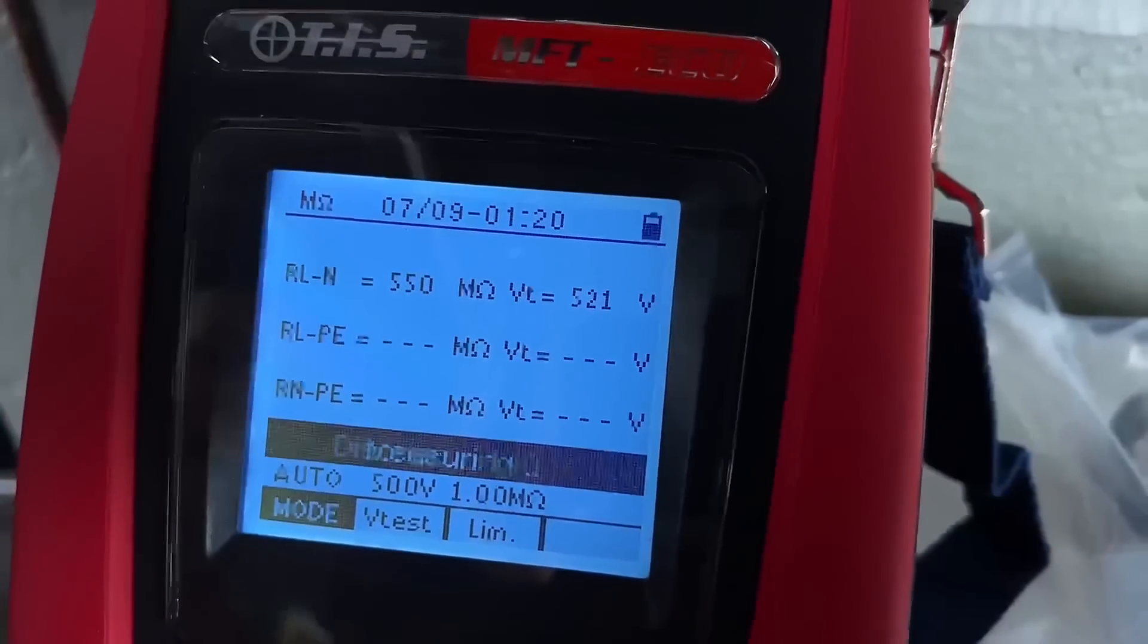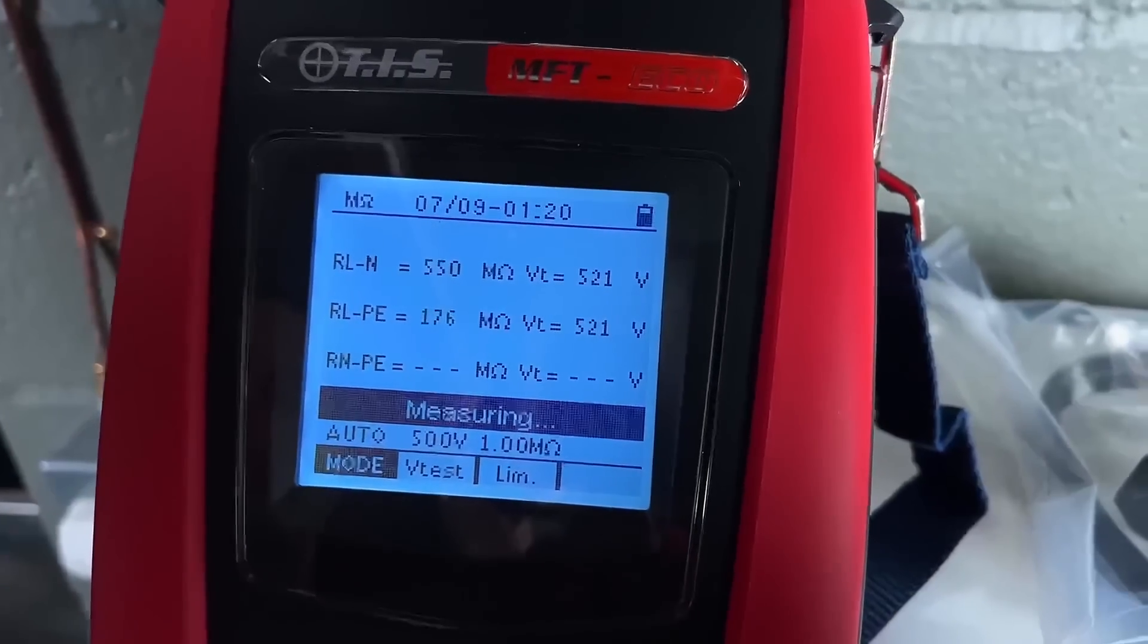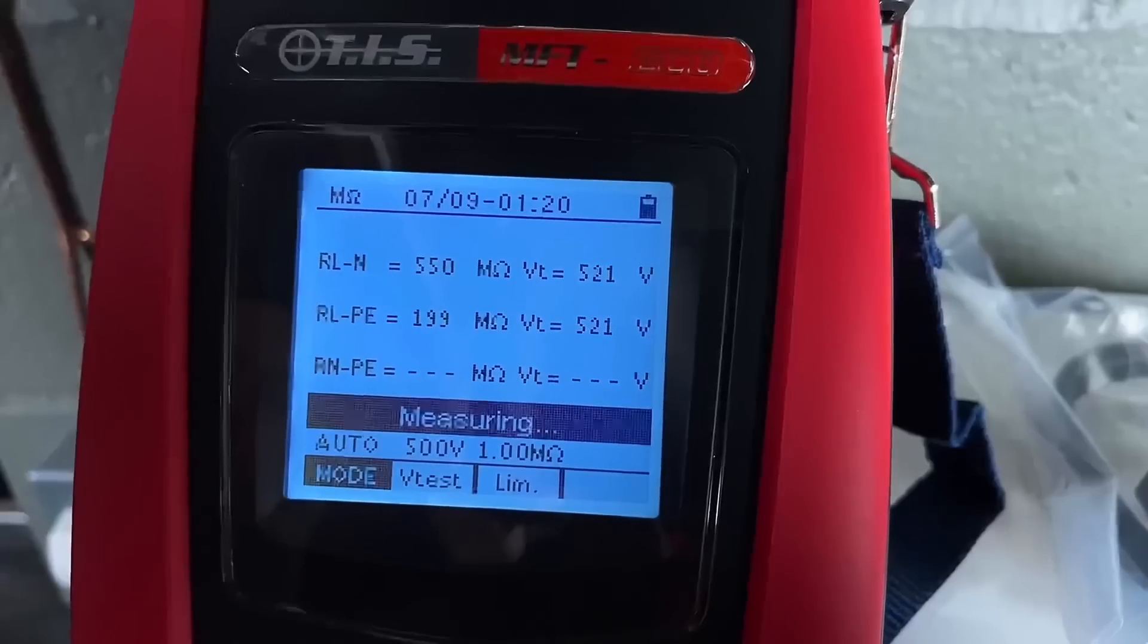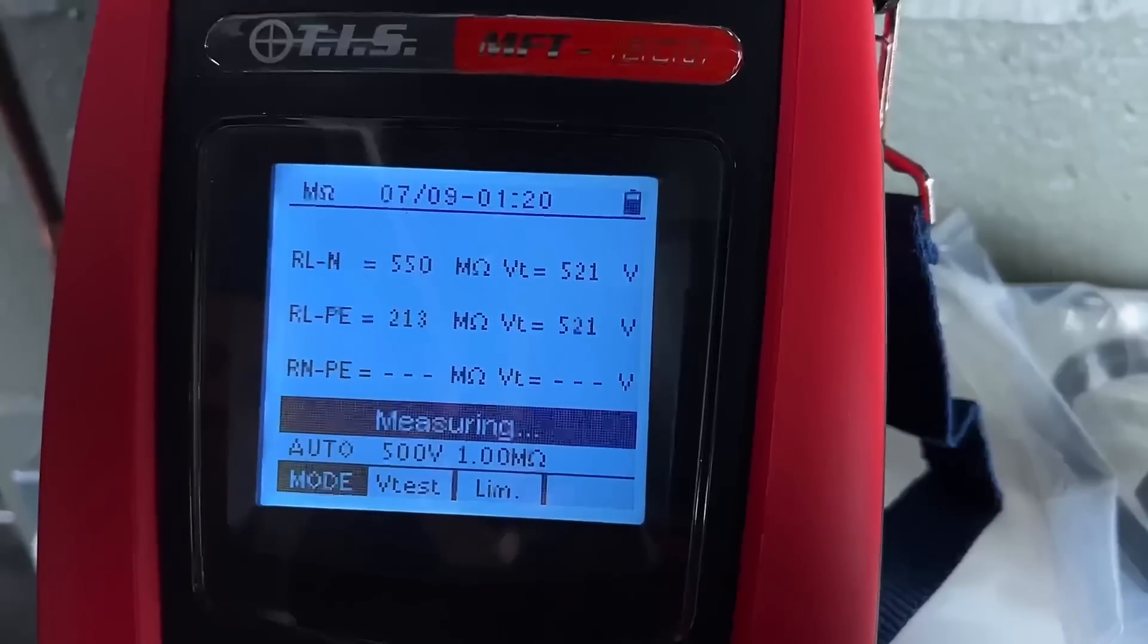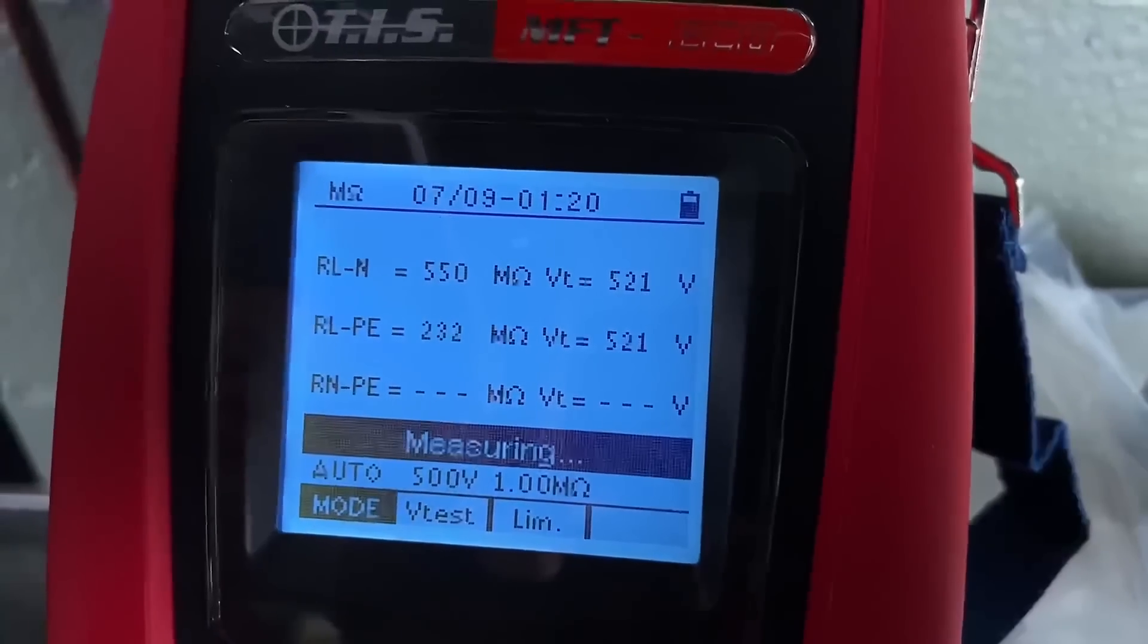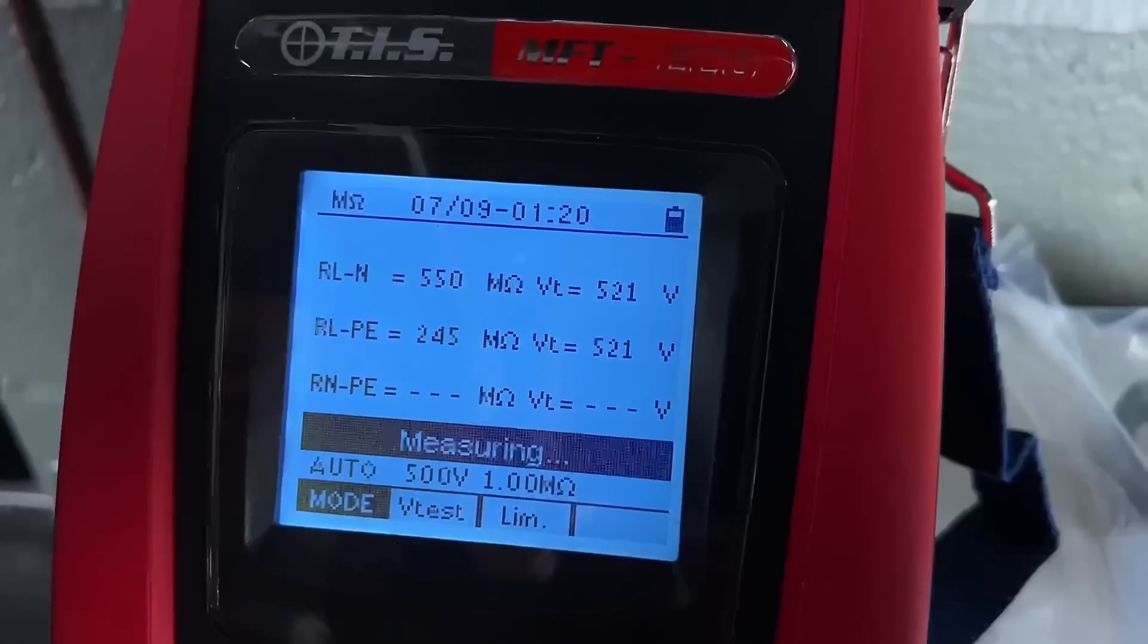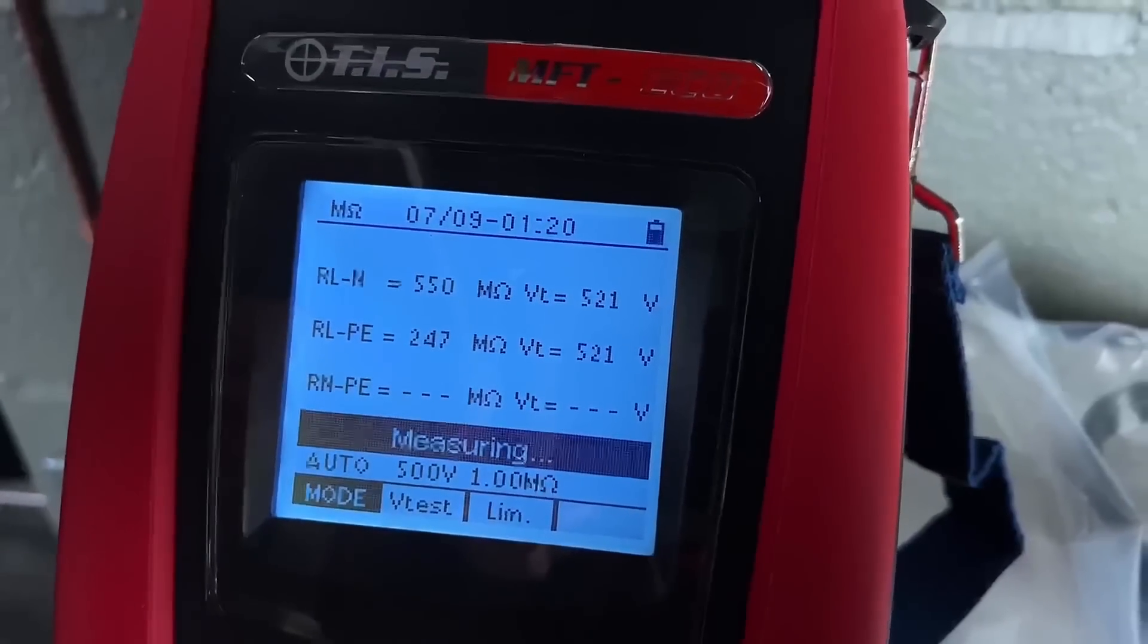Once it's happy with the line and neutral, it will drop down and do line and protective earth and then neutral and protective earth. So we've done the first one now, so it's actually tested over 500 volts and it has an insulation resistance test reading of 550 mega ohms. And now we're on to the second one and we're cycling through. So I've got my hands in the consumer unit, I'm looking at the screen here, I'm not going to press any test buttons on the machine.